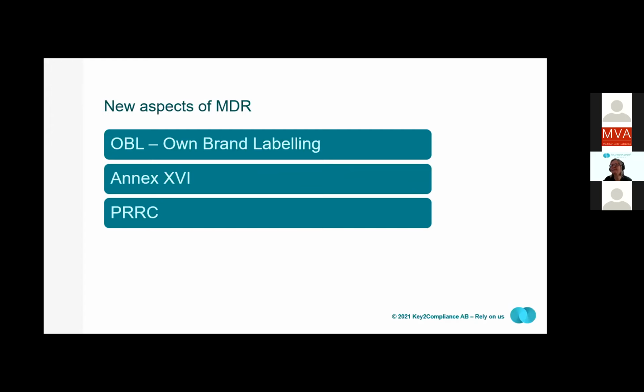I will also just mention, if your device today is an OBL, an own brand labeling, you need to make sure that you have a full technical file for your device according to Article 10. This is something that has been made more clear with the MDR. For MDD, you could rely on the CE mark of the original equipment manufacturer, the OEM, that had designed and manufactured the device that you would then sell as your own brand. And even if you would have an agreement with your OEM to transfer the full technical file, you still need to implement the devices into your quality management system and also appoint the person responsible for regulatory compliance.